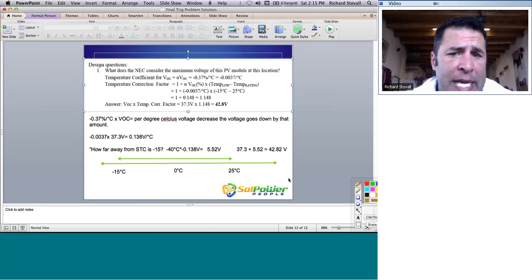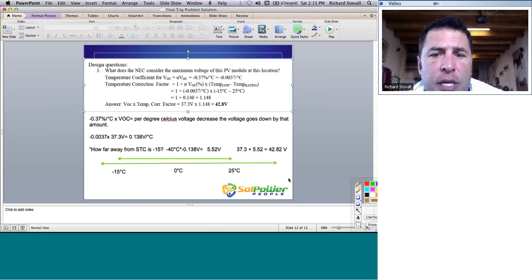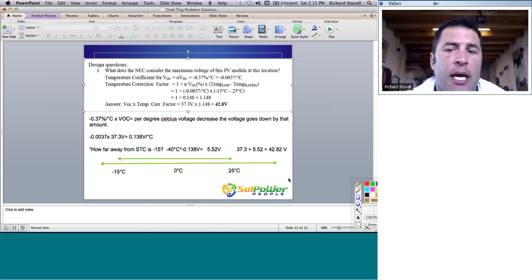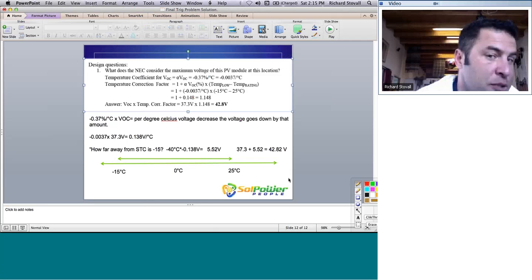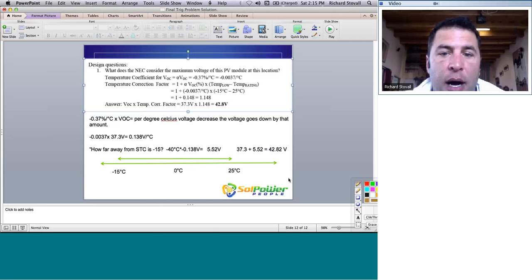It's just personal preference. He takes that percentage and applies it straight against the degree temperature change of 40. He basically adds 14.8%.